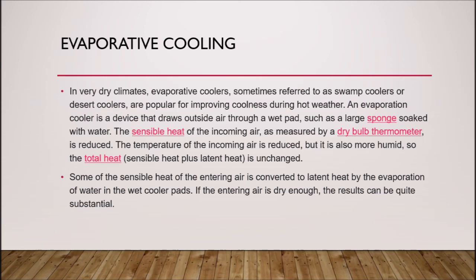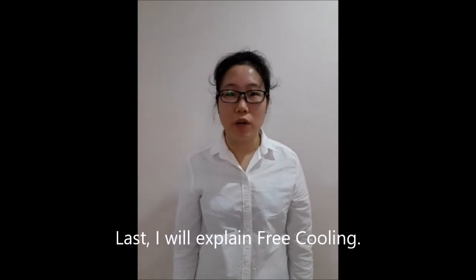Some of the sensible heat of the entering air is converted to latent heat by the evaporation of water in the wet cooler pads. If the entering air is dry enough, the result can be quite substantial. Last, I will explain free cooling.